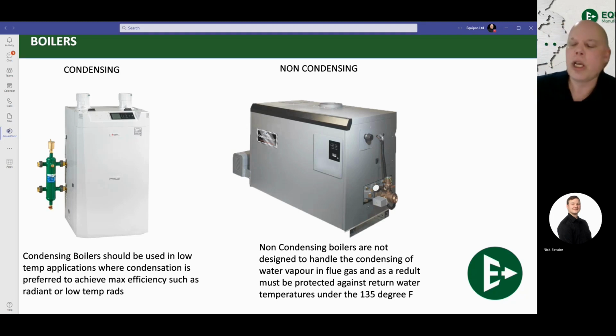So for non-condensing, you want that return temperature to be nice and high, anything over 140, 145, 150, something like that. A good way to think about it is a condensing boiler is extremely good at low temperature applications, which is the future of hydronics, starting yesterday. And for non-condensing, you want to see more of your high temperature applications, such as air handlers and radiators, where you want that 160 to 180 input to get the BTUs that you want.